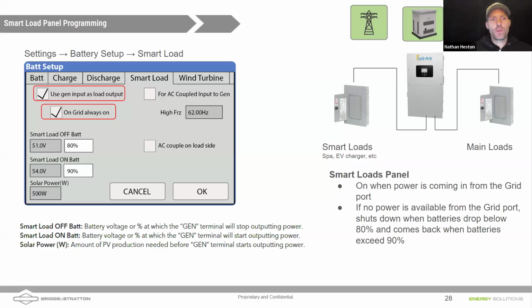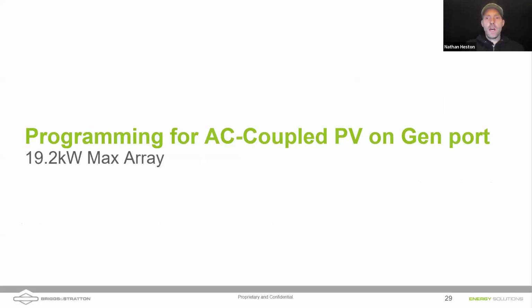Daniel, what's the reason for the discrepancy between the 80 and 90% there? Well, you don't want it necessarily flickering on and off. Yes. So you want to give a little buffer there so that it can charge up and then have that ability to come off. If it was right at the same value, you might have it shutting on and off rapidly. Frequently, exactly. Yeah, and that's what we can see in the bottom right corner here. I've just noted why that happens in a bullet point.